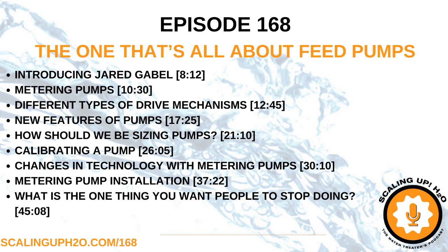is a good idea. When do you need to calibrate a pump and what is that procedure? Well, calibration is done once the pump is installed in the environment where it's going to operate. If I were to calibrate a pump on my desktop and then ship it to you, and you install it at a pressure that's much different, so the back pressure I've tested against is different than yours, maybe by 20 or 40 PSI, then the calibration is going to be all out of whack by the time you install it. So install it, get the pump to feel the back pressure it needs to pump against, and then calibrate it. And what we always say is calibrate it on the suction side.